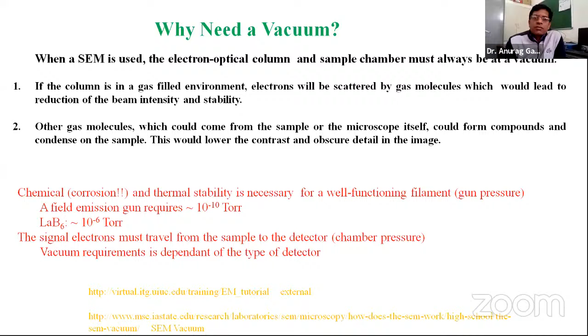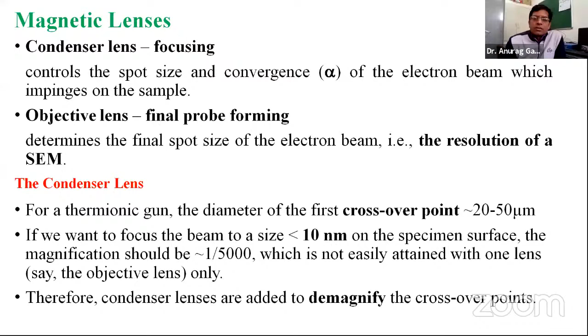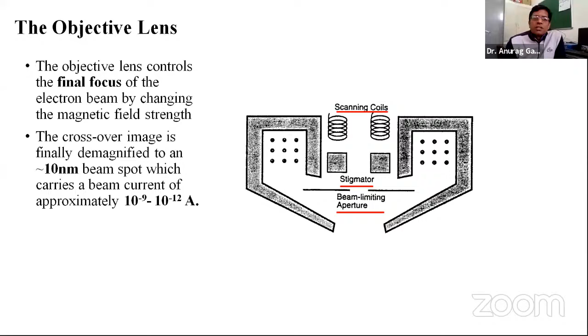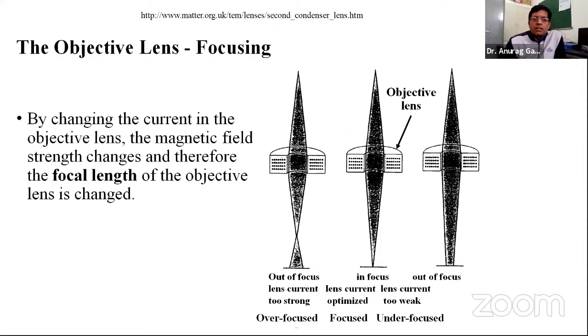Now these are some lenses that are being used. Condenser lenses are used for focusing the electron beam. The objective lens does the final probe formation, so that it is highly focused. The objective lens controls the final focus of the electron beam by changing the magnetic field, and the crossover image can finally be demagnified to about 10 nanometer. The objective lens changes the current to change the focal length, and that gives a raster pattern.